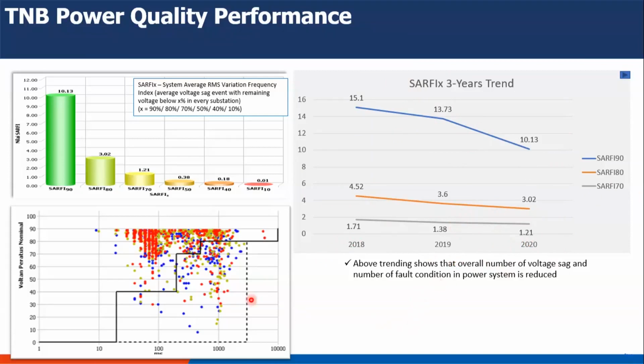This graph shows the occurrences. The red, yellow, blue are the phases, and this axis is the voltage percentage. You can see from here that most voltage sags happen in the upper region. This table represents the immunity curve, and most voltage sags happen above the immunity curve. So by right, customers who have enough immunity and somewhat follow this immunity curve won't be so much affected.